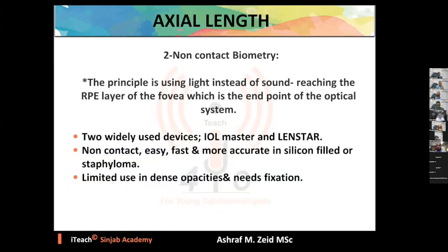The principle is using light instead of sound, reaching the retinal pigment epithelium of the fovea, which is the endpoint of the actual optical system. Two widely used devices are the IOL Master and Lenstar. Also, Aladdin from Topcon is very nice. It's non-contact, easy and fast, and more accurate in special situations like silicone-filled eyes or staphyloma. But it has limited use in dense opacities and needs fixation because it depends on light.